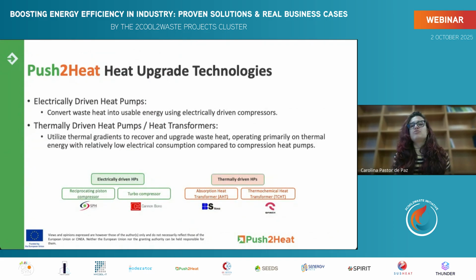Push-to-Heat has 4 main technologies that can be classified into electrically driven heat pumps and heat transformers. The first ones convert waste heat into useful heat with compressors - one piston compressor and one turbo compressor. The other ones utilize thermal gradients to recover and upgrade this waste heat, operating primarily on thermal energy with relatively low electrical consumption compared to the previous ones. Here we have an absorption heat transformer and a thermochemical heat transformer.